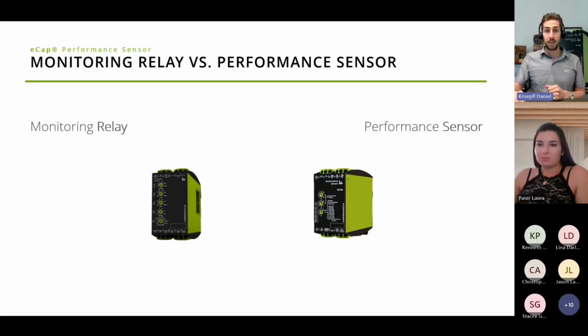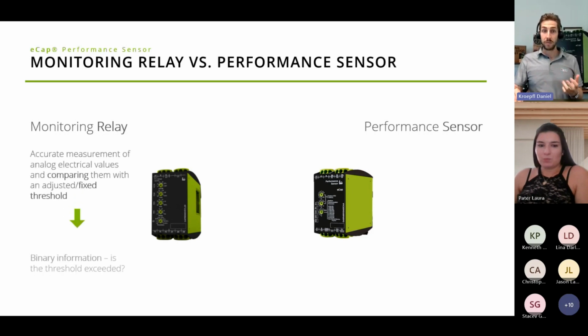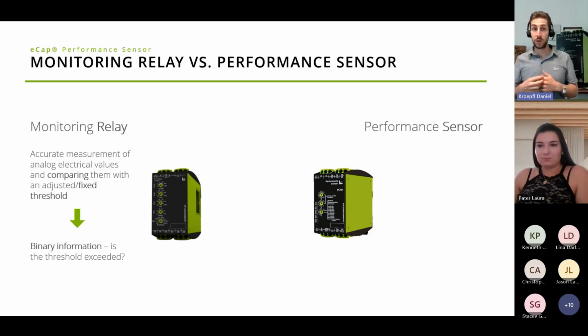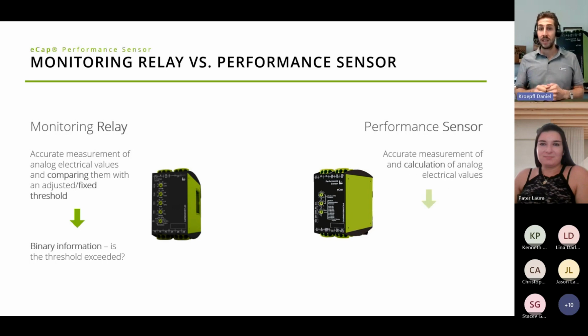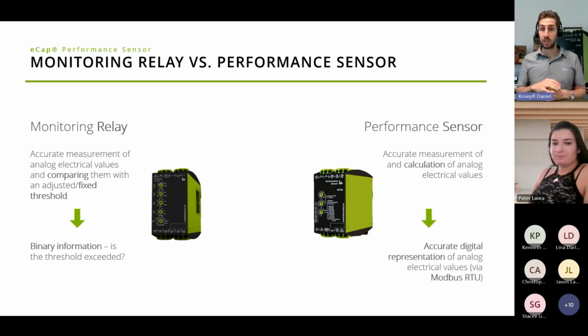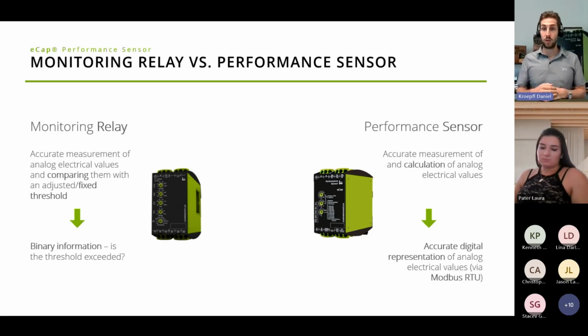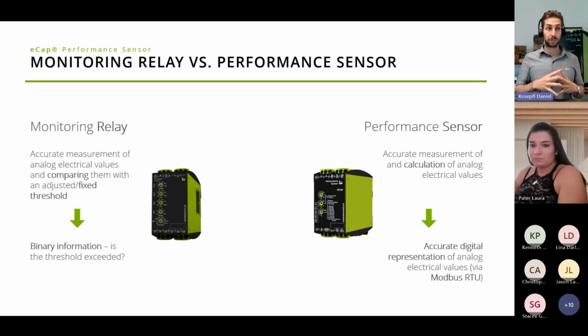As I said, with monitoring relays you can get an accurate measurement, but it's a fixed threshold and you get binary information, meaning the relay switches on or off. That works for some applications, but not for ones where you want a real peek into what the control application is doing. That's why we decided to give this energy sensor a Modbus RTU interface, turning those analog electrical values into digital data that you can process in your HMI or SCADA system, for example.